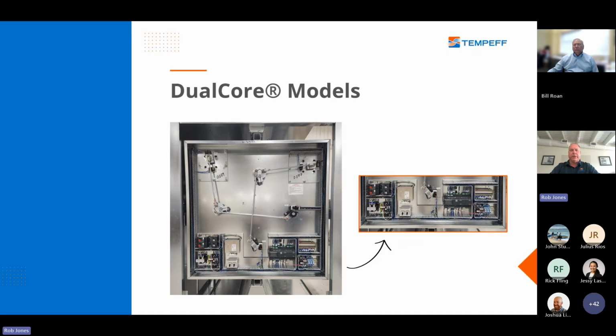This is what the internal control section looks like. You have your damper arms here that are controlling the damper that's in behind, along with the actuator. And we have our Schneider PLC controller with the BMS connections in the bottom here. We also have a manual and auto switch. So if there is no BMS system, the Schneider controller will run our unit. It works in both standalone mode and with a BMS system. Obviously, all our products are BACnet capable.